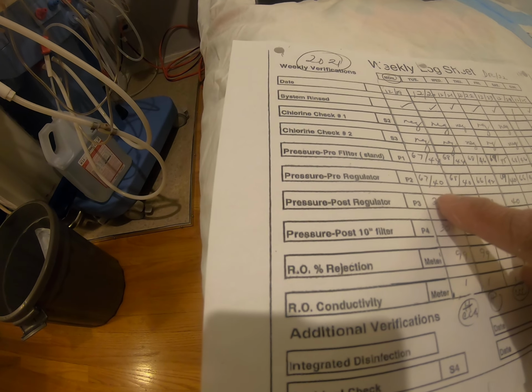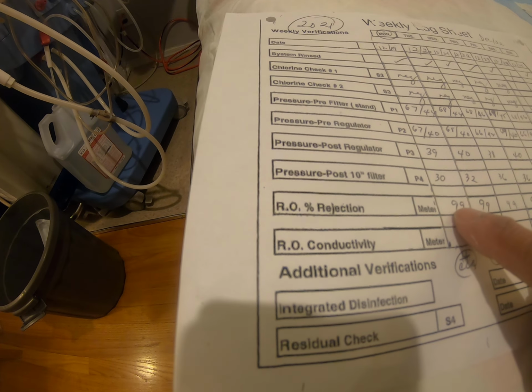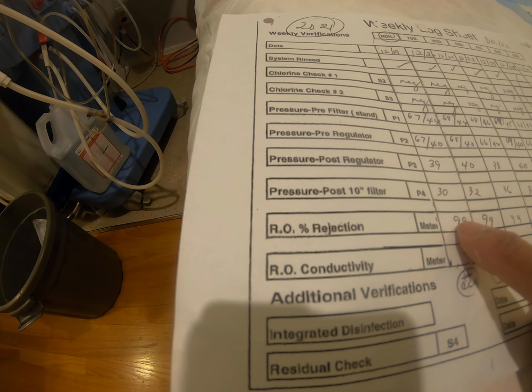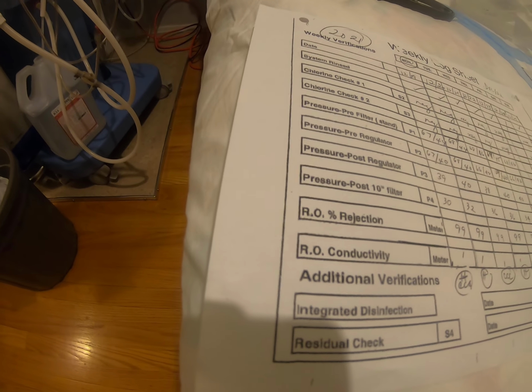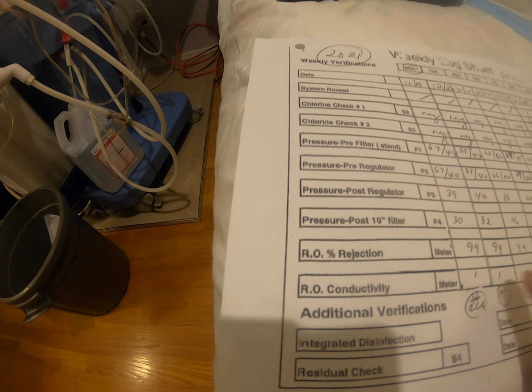Your pressure 1 and pressure 2, you get the higher numbers; your pressure 3 and pressure 4, you get the lower numbers. Your rejection, you put there, usually 95 to 99 — here we got 99%. And the conductivity is usually 1 to 2; we get 1. And that's it, you're done.